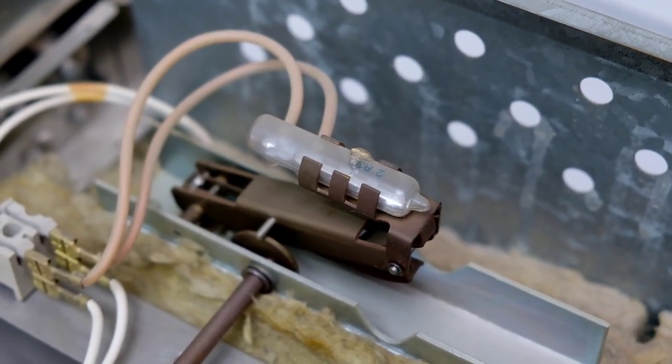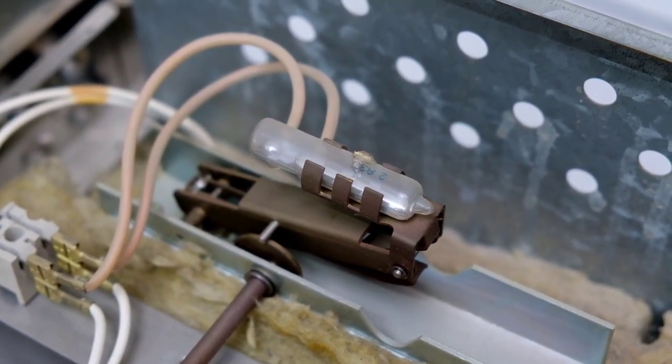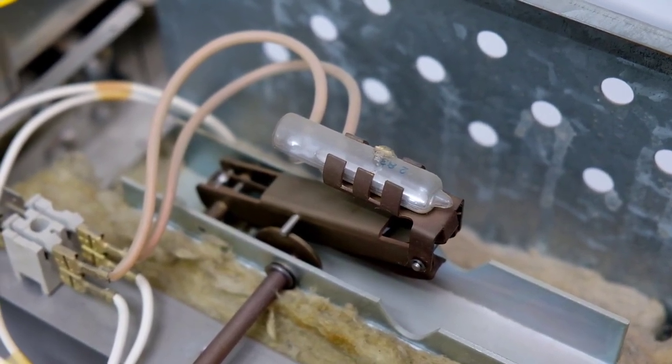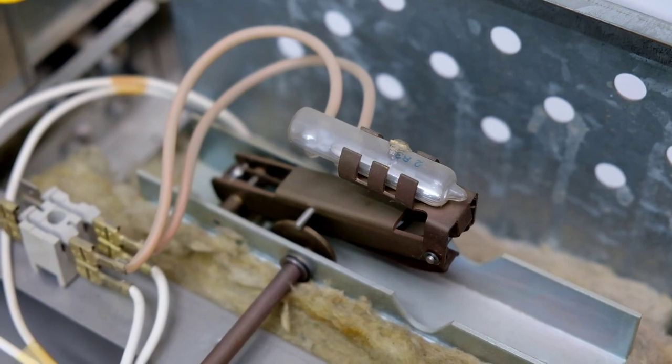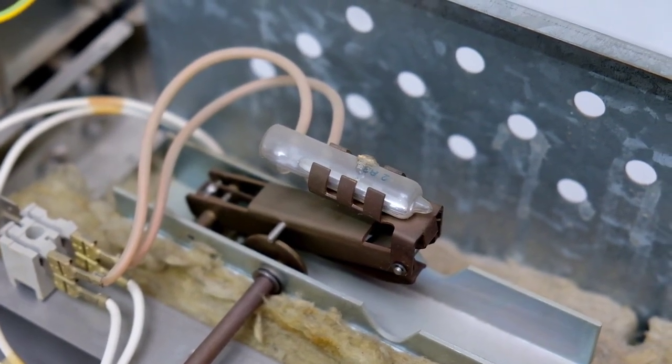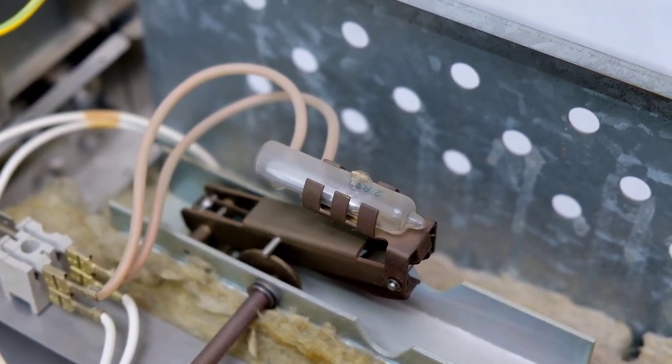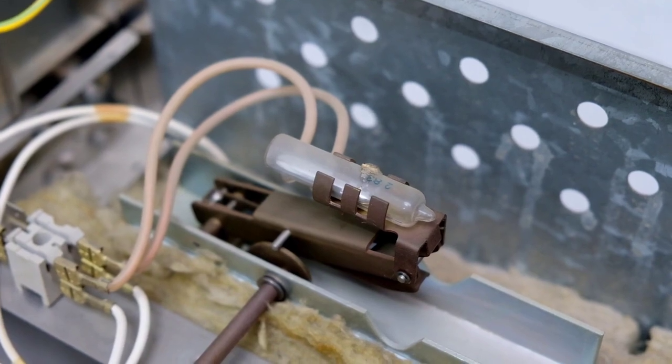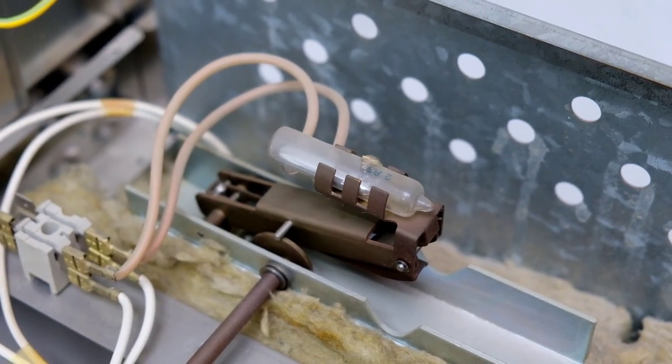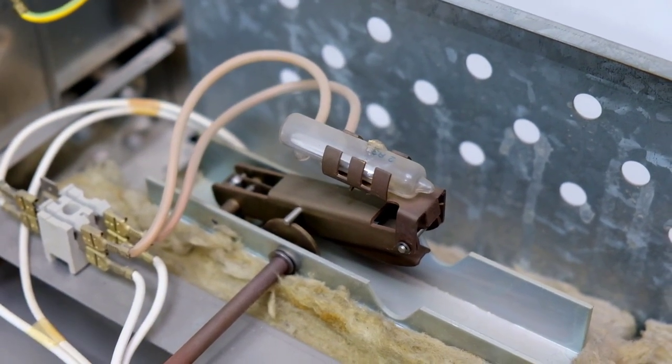One of the biggest advantages of this system is the fact that it can switch high amounts of current without deteriorating the contacts, like in a relay, where the contacts can pit and will be damaged after a lot of cycles. Here, the mercury is not affected at all. So this oven, this thermostat will practically work forever.